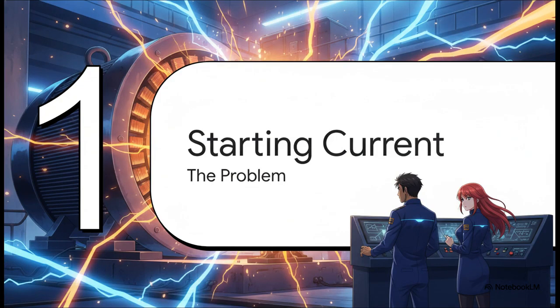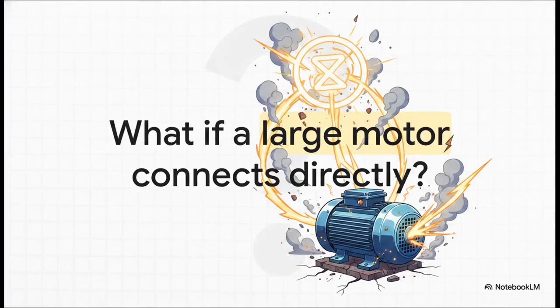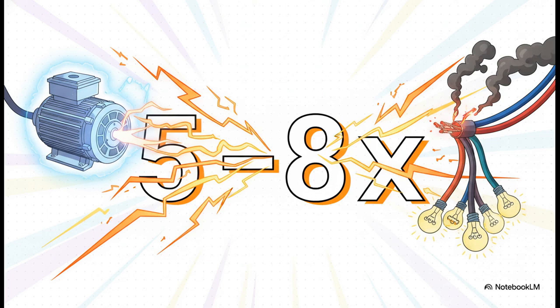Section 1, the starting current problem. Have you ever wondered what actually happens when you flip the switch on those massive motors at a large pump station? It's not just a simple hum. So ask yourself this. What happens if a large induction motor is connected directly to the power supply? On the outside, it might seem completely fine, but inside the electrical system, you're literally opening the door to a disaster. The scale of that disaster really comes down to this number, 5 to 8.